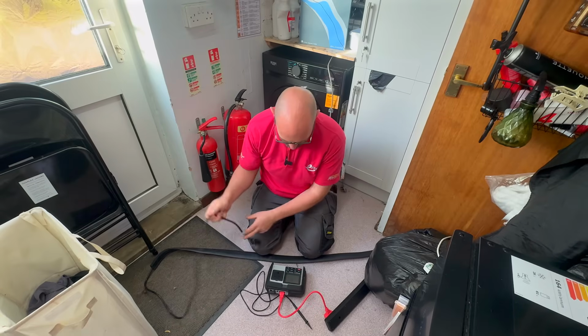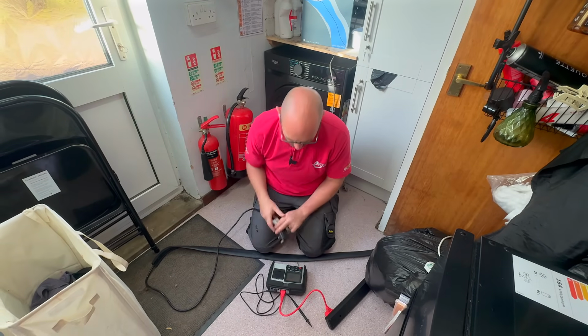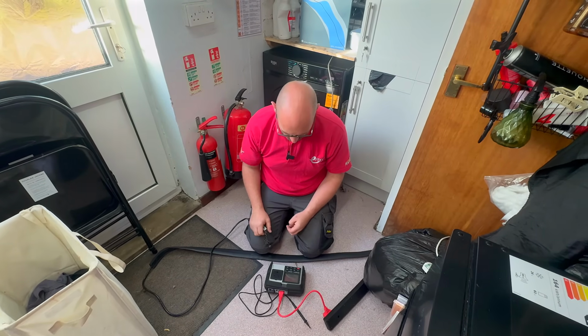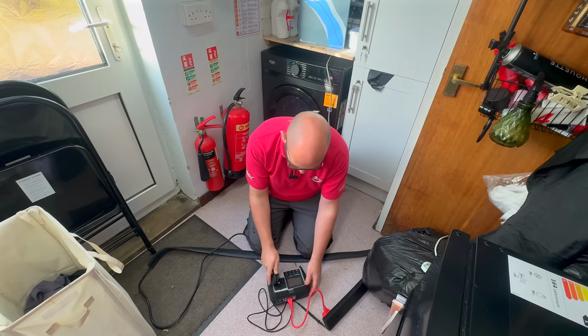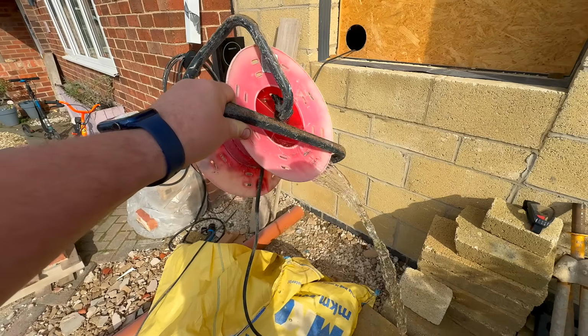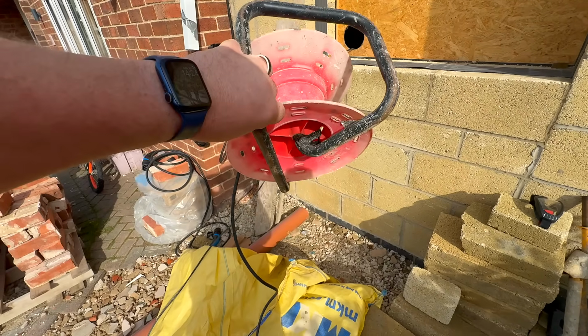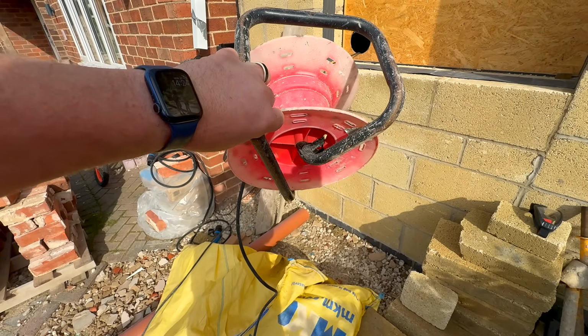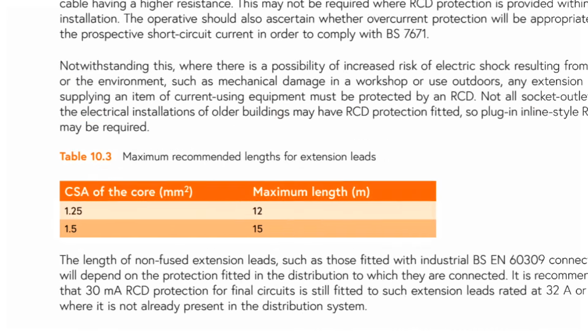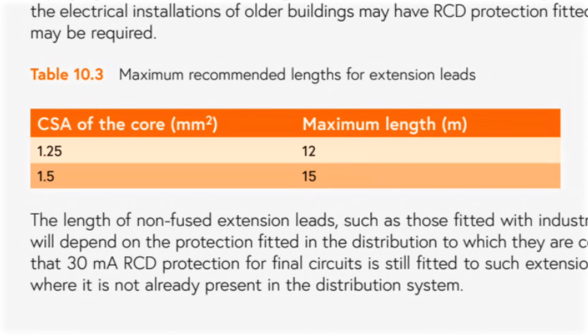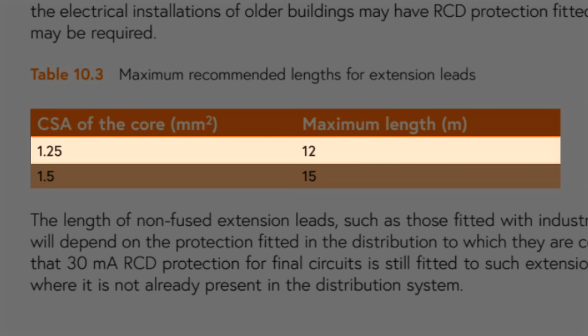Because this is a class 1, an earth continuity test is required. That confirms the protective conductor runs cleanly from the plug all the way to the socket end. If the extension lead has a metal drum or frame, that metalwork must also be verified as an exposed conductive part. The code also limits the length of 13 amp fused extensions. A 1.25mm squared lead generally shouldn't exceed around 12 meters and a 1.5mm squared lead around 15 meters. Longer cables reduce fault currents and compromise disconnection times.